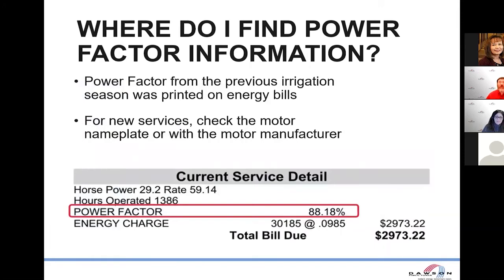All right, so here's where you can find your power factor information, right? If you've got a previous season's bill, particularly this fall's bill, look under the current service detail section, and you'll see second from the bottom line there is power factor, right? This particular system has a power factor of 88.18%. They're awful close to 90. So that's going to be a real tough decision for them as to whether they need to improve or not. They may be okay with just paying the additional charge. It might be cheaper than having someone come put a capacitor on.